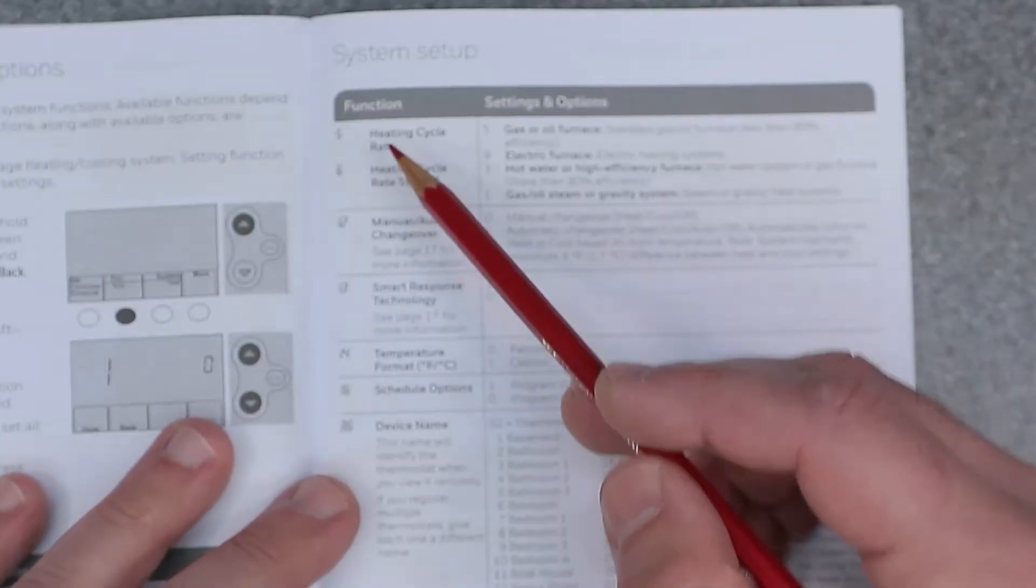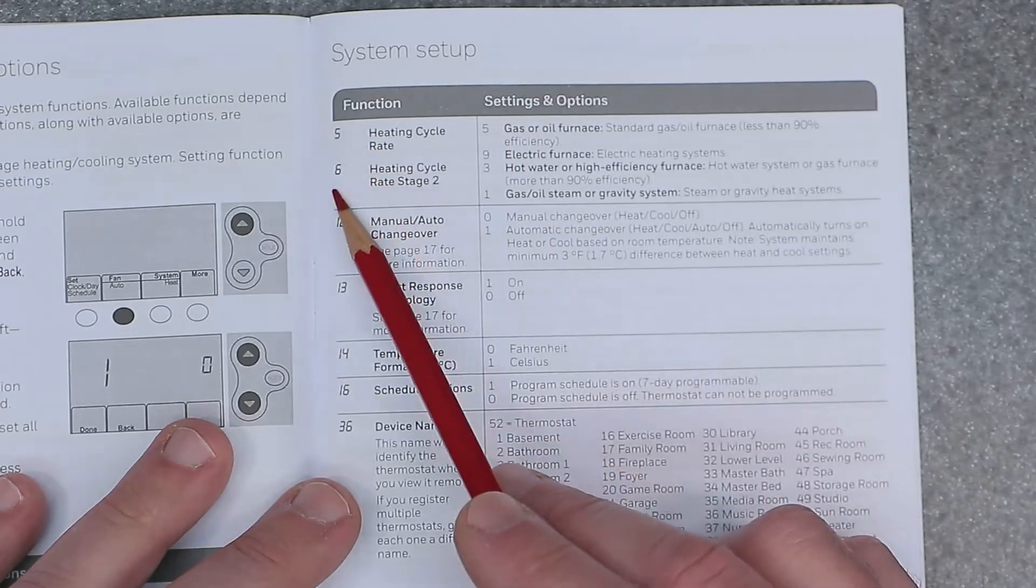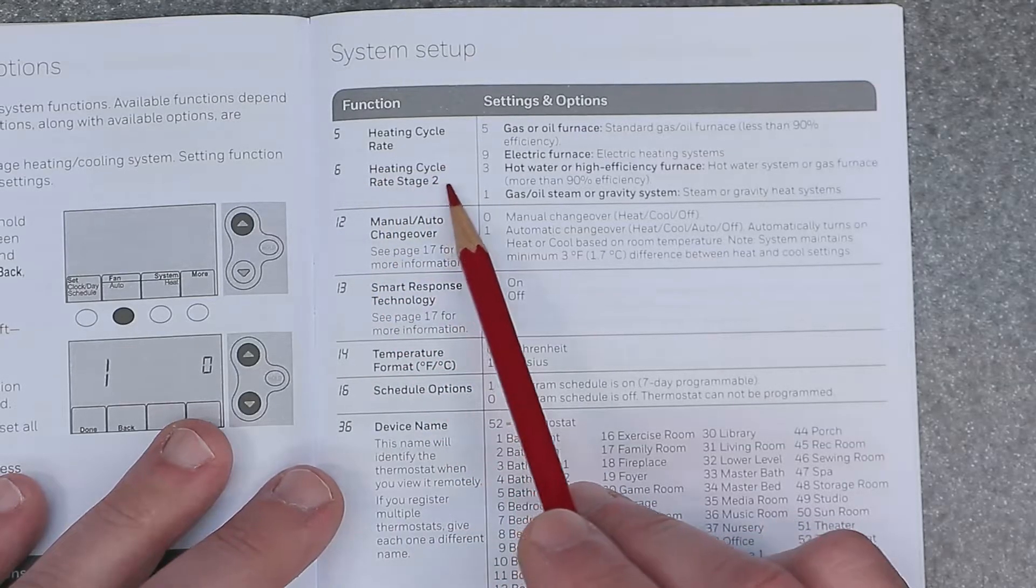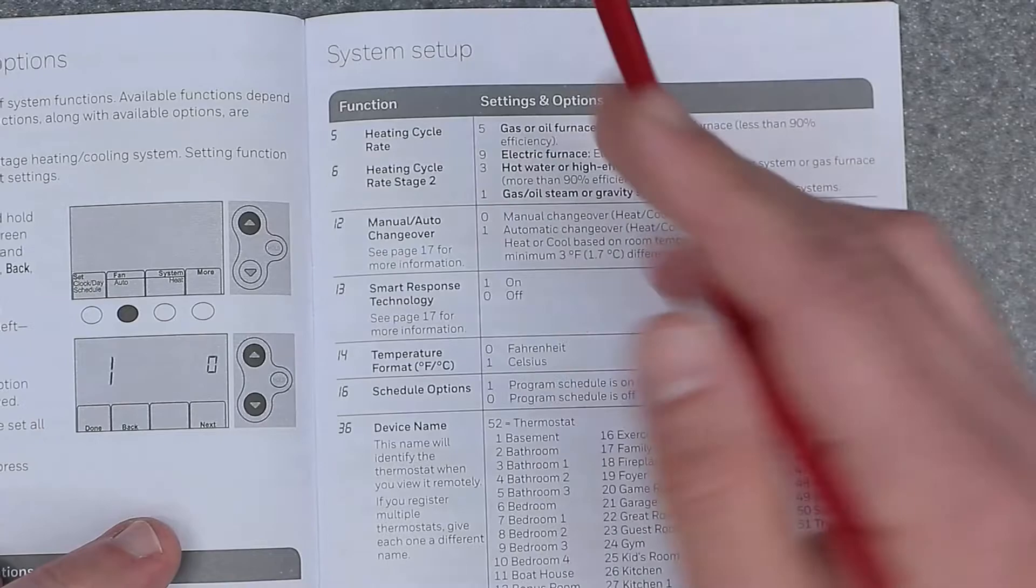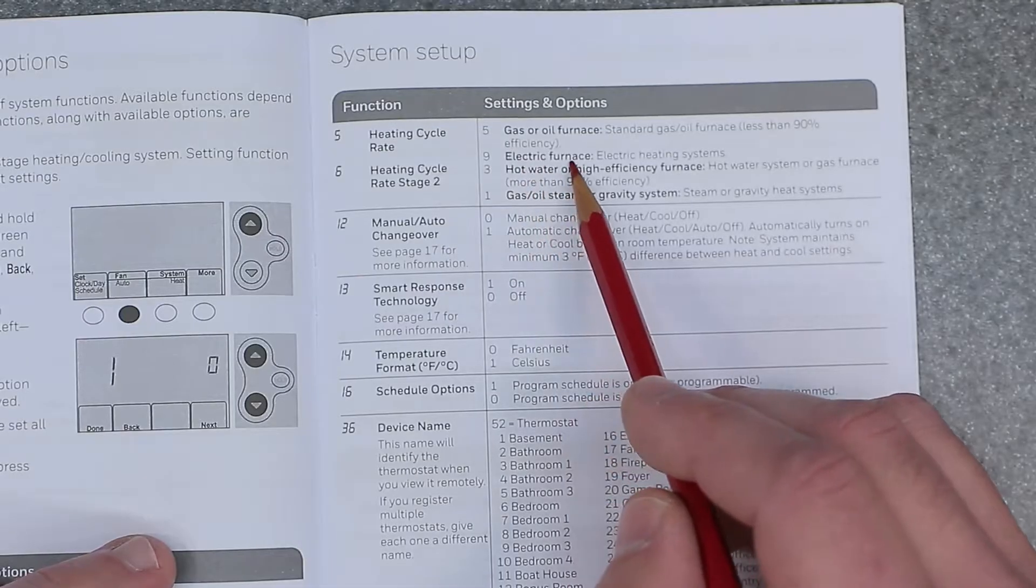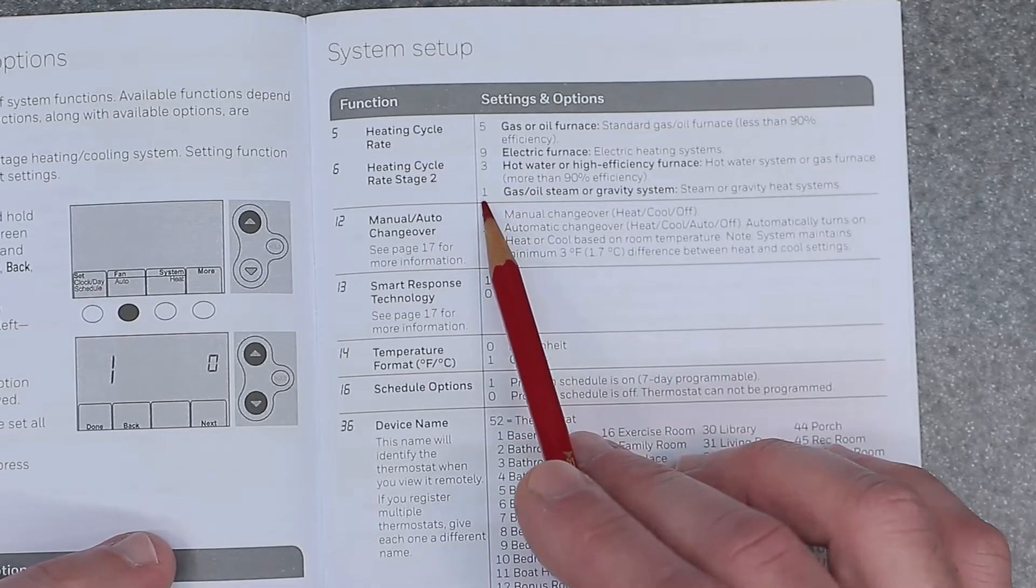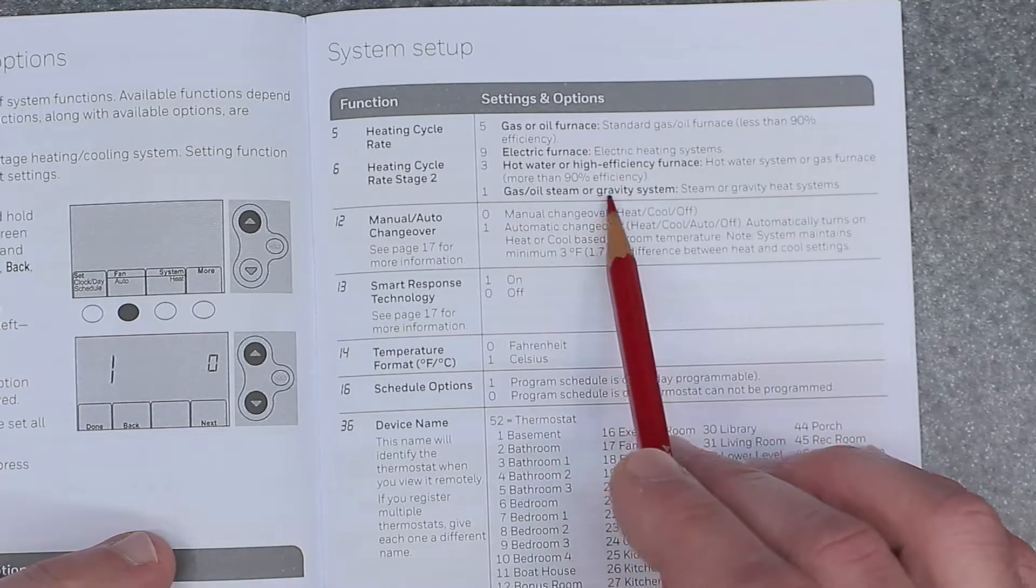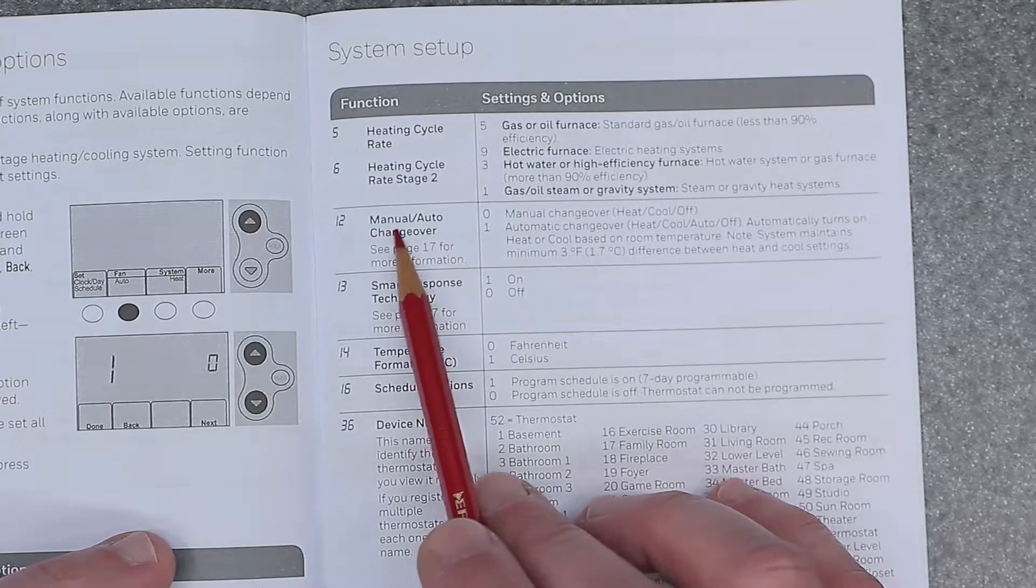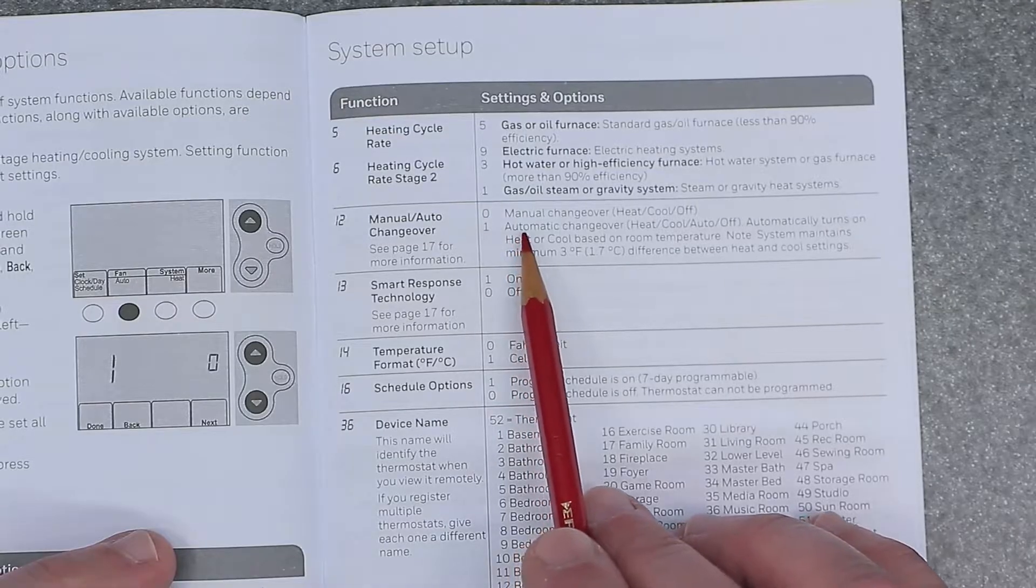Function number five is going to be heating cycle rate. And that's the same thing with number six. So number five is heating cycle rate. And six is heating cycle rate stage two. So these are going to have the same options on the right hand side. So we have five is gas or oil furnace. Nine is electric furnace. Three is hot water or high efficiency furnace. Number one is going to be gas, oil, steam, or gravity system. Function number 12 is manual or auto changeover. Zero is going to equal manual changeover. One is going to be automatic changeover.